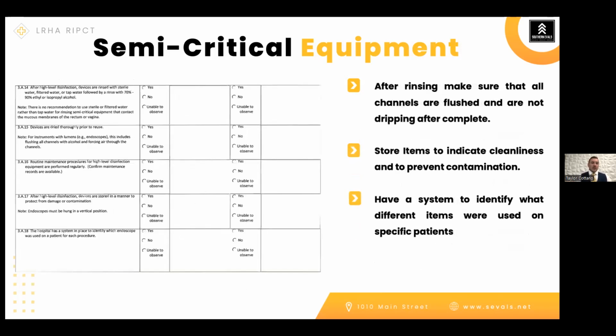Semi-critical equipment, moving on. After rinsing, you want to make sure that all of your channels are flushed and are not dripping after complete. Whenever we hang these items or store these items, are they visually clean, or are they leaking, and do they have things on those? Make sure that, especially with endoscopes, if you rinse those channels, you flush those, you dry those things out, and you store those properly. On to our next item.